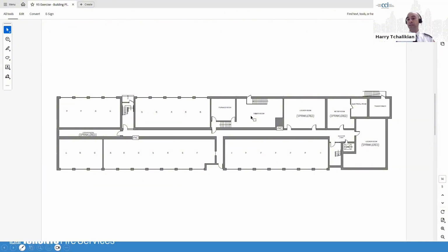What is the requirement in the fire code? So I'll read it. 216.2.1, sentence 2. Where a fuel burning appliance is installed in a building, but not within a suite of a residential occupancy or a care occupancy, a carbon monoxide alarm shall be installed, A, in the service room or area where the appliance is installed. So right there, boiler room, you need one. Right here, where my cursor is, furnace room, you need one there as well.